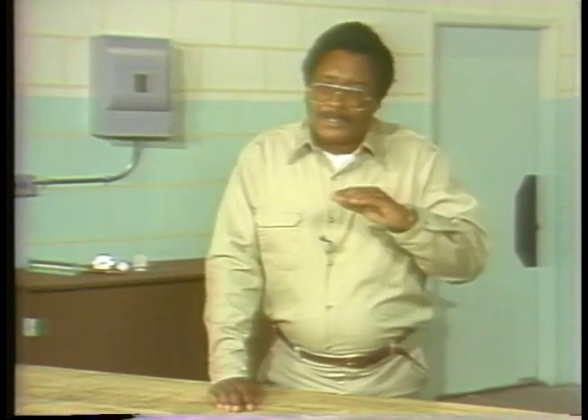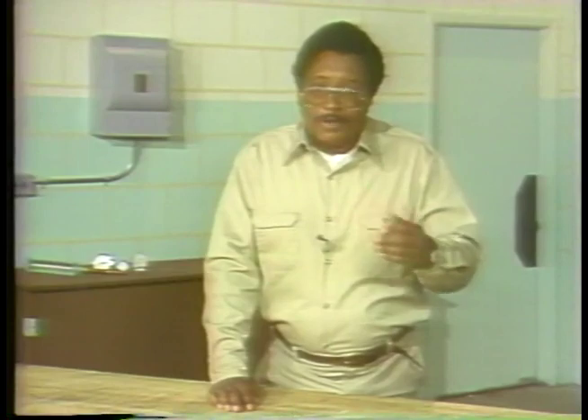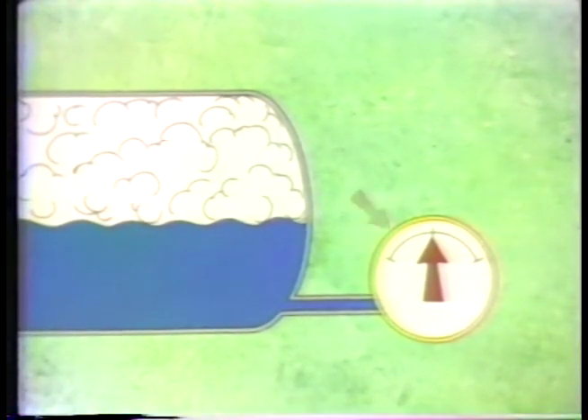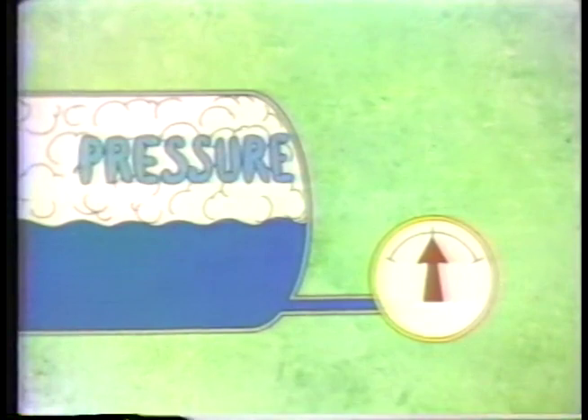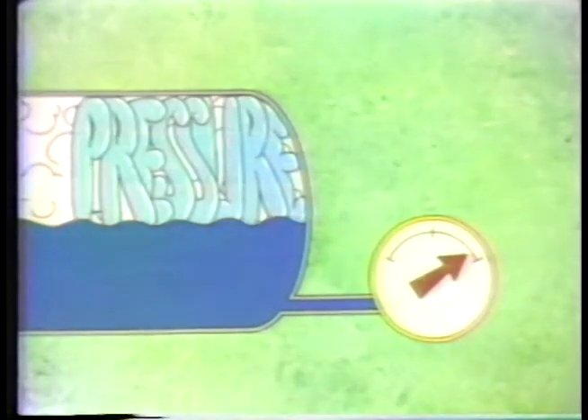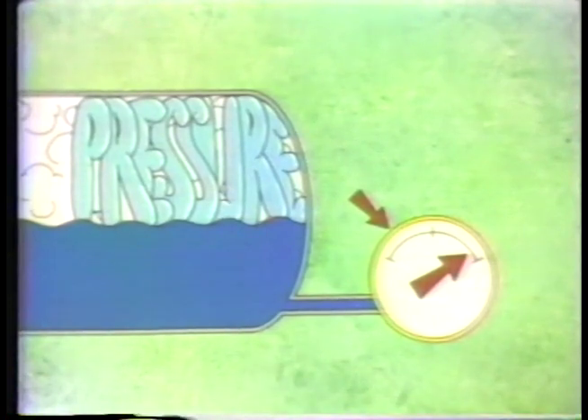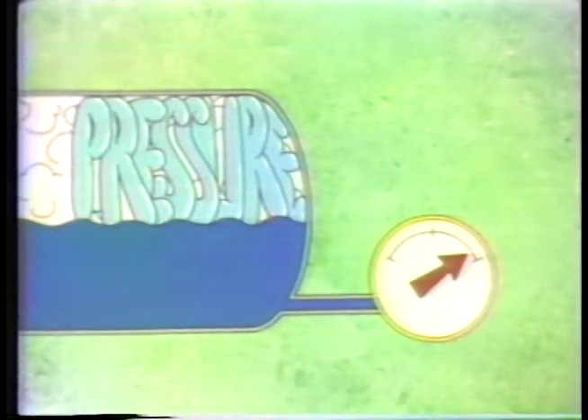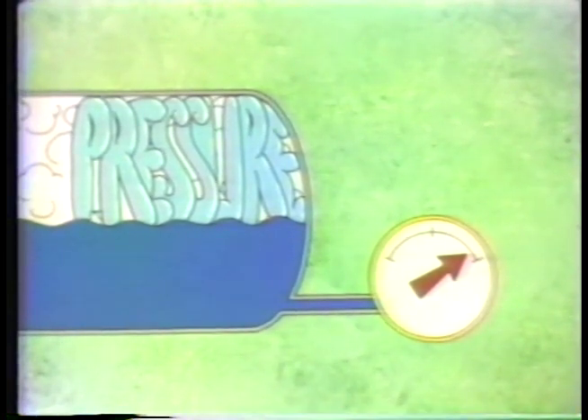However, this design doesn't work well when there's a pressure on the tank or vessel where level is being measured — one example would be a boiler drum. If we used this pressure gauge to measure level in a boiler drum, we immediately run into two problems. First, the pressure inside a boiler drum changes, and these fluctuations would be sensed by the level indicator. So if the pressure inside the boiler drum changes but the level remains the same, the indicator would show that level changed when it really didn't.